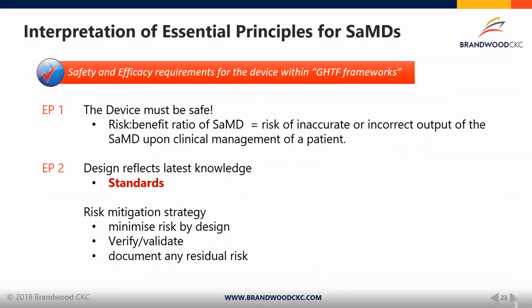So once you've determined the software classification, obviously under the regulatory framework of the GHTF, as I mentioned before, one of the key elements is to comply with essential principles for safety and effectiveness. No matter if you're developing a software or hardware medical device, you still need to demonstrate compliance with those safety and effectiveness requirements. Obviously, essential principles have to be interpreted in the context of software.